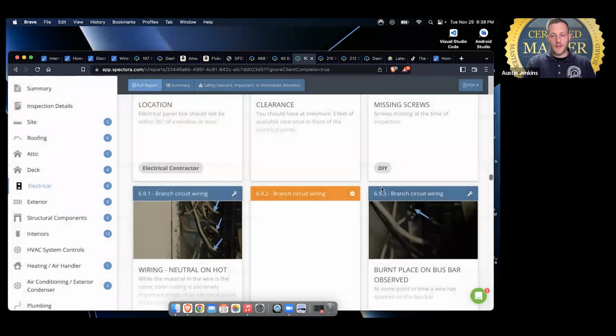One thing that surprisingly a lot of people don't write up, but I still do, is when a white wire — normally a neutral — is used as a hot conductor. Most often this happens on a 220/240 circuit, because using the white conductor as a hot saves money instead of buying a 12-3 or 10-3 wire. You are allowed to do this, but it needs to be marked with black ink or black electrical tape. That's one I see all the time.